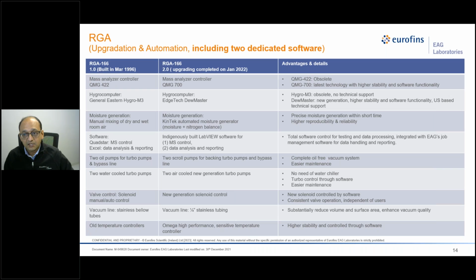The first thing we changed is the analyzer from Pfeiffer Vacuum, which was the QMG 422, and now we have the QMG 700, almost 3 generations of development in the main controller that controls the mass spec system. The second thing is the computer. We moved to a newer generation computer, which is readily available and easy to maintain. We were also taking care of parts which are obsolete, still in operation but without any technical support. We wanted to get away from those kinds of parts, and that's the reason we moved away from the earlier generation of mass analyzer as well as the computer.